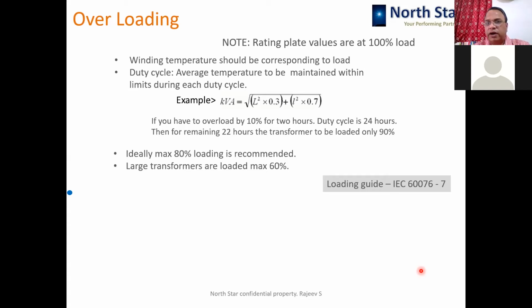Many times, because of some problem in the WTI, maybe wrong calibration or wrong setting from the factory itself, it shows a lower or higher temperature. So that calibration needs to be done. The duty cycle has to be maintained in any case, because exceeding the duty cycle is definitely a recipe for killing the transformer very fast.